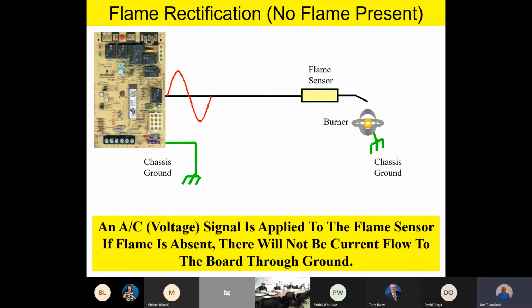But the science behind it is this. Flame rectification: anytime the furnace is powered up, we have AC voltage going to the flame sensor, and it's line voltage driven. So if there's no flame present, nothing happens. You've just got AC voltage going to this flame sensor that's not touching anything. It's just got voltage on it, and there will not be any current flow through the board or through the ground system if there's no flame present.